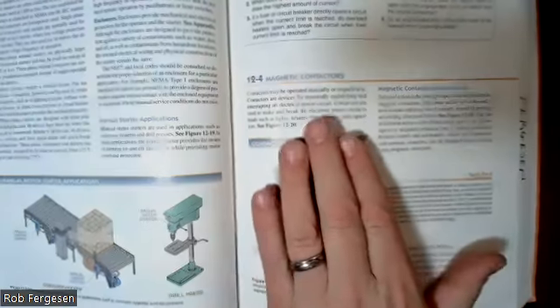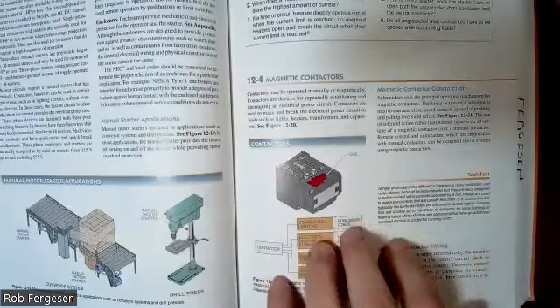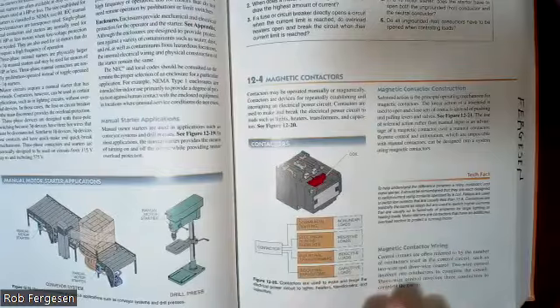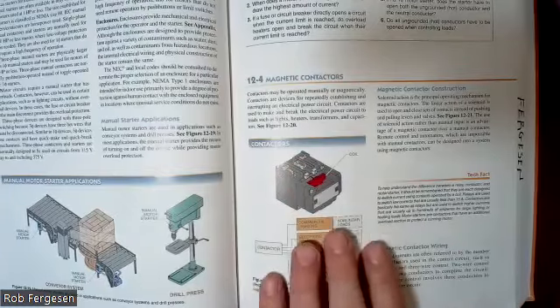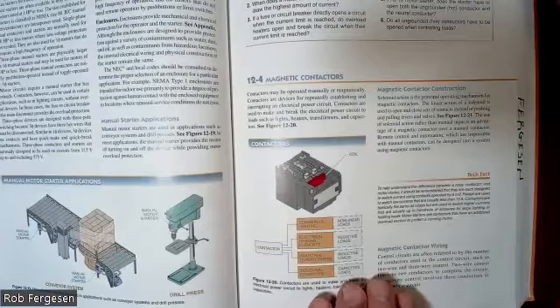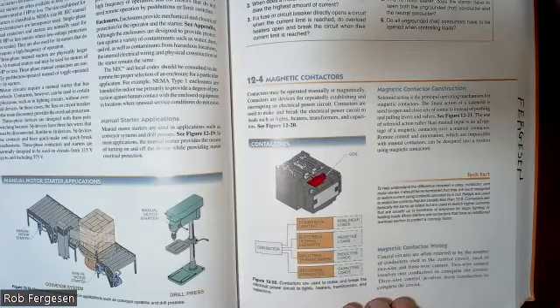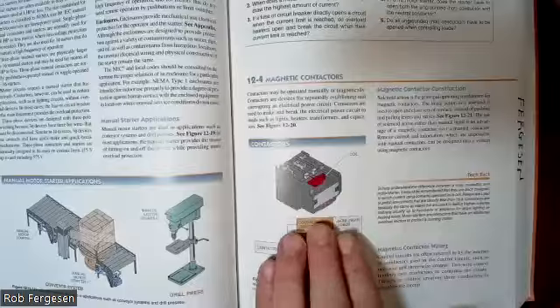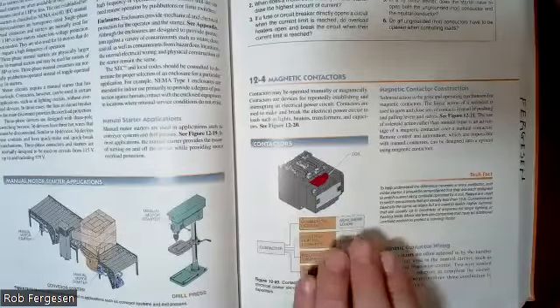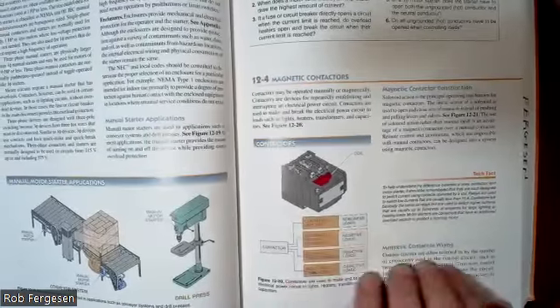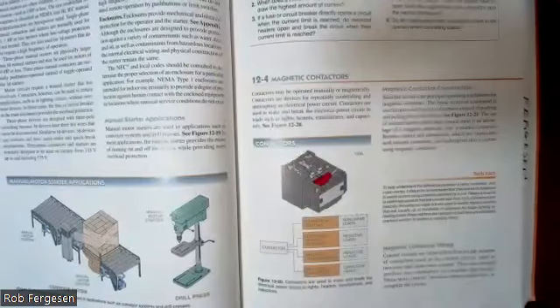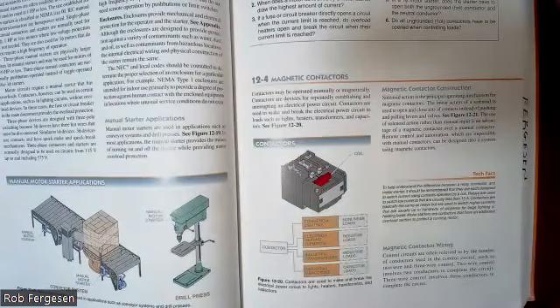And this is exactly the same as a relay. A relay is identical to a contactor, except usually relays are configured to handle much lower current, whereas a contactor is designed to handle big current motors, a lot of inrush. And if you're going to buy something to turn on and off a lot of electrical power, a contactor is the way you go.